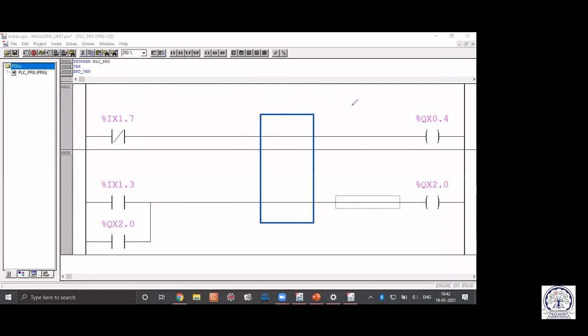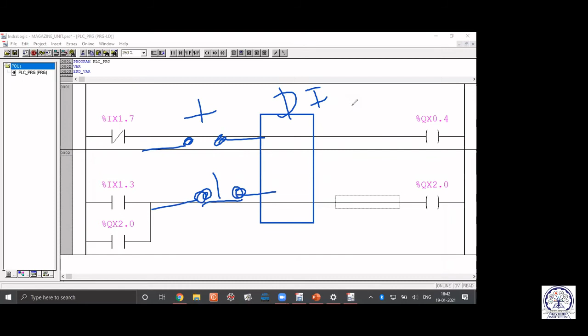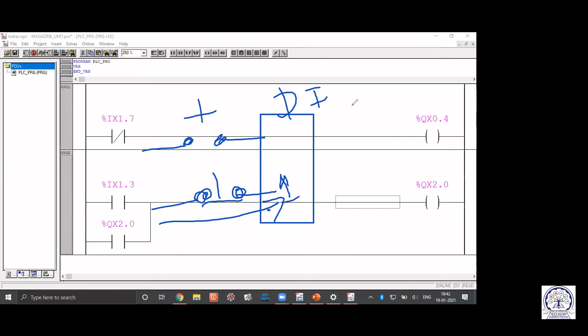Okay, just a minute, let me write it, note it down. Suppose this is a digital input module, a DI module, and you have a start push button here that is wired in the NO form. But if you have a stop push button, by default it is connected in NC state. So that means supply is already coming to this point, and this state is already 1. So what do I have to take? If you take this terminal as NC and it gets a command, this NC will change to NO. Okay. Let me show you in the program.